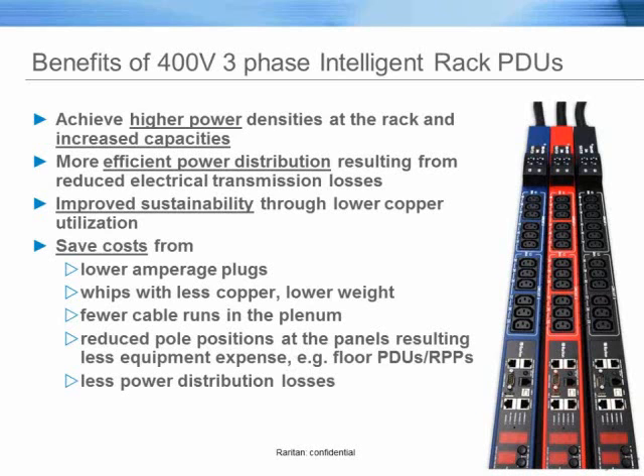Lower copper, plain and simple. That's physical, not just in the ethos, like saving power by using less copper - that's a physical cost savings out there. Also in deployment: lower amperage plugs, fewer whips, fewer cable runs, fewer pole positions. Again, this is 3-phase, so we're taking up 3 poles on the breaker panel. The more poles you take up, the more money it costs. So by deploying 400-volt 3-phase, we can save a lot of money at the data center and provide a ton of power. I think that's win-win for everybody.